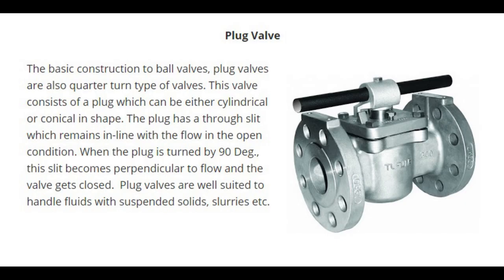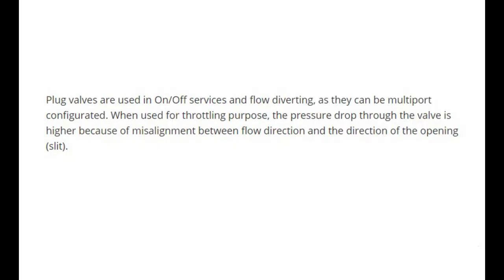Plug valves are similar in basic construction to ball valves and are also a quarter-turn type. This valve consists of a plug which can be either cylindrical or conical in shape. The plug has a through-slit which remains in line with the flow in the open condition. When the plug is turned 90 degrees, the slit becomes perpendicular to flow and the valve closes. Plug valves are well suited to handle fluids with suspended solids and slurries, and are used in on/off service and flow diverting. When used for throttling, the pressure drop is higher due to misalignment between flow direction and the direction of the opening slit.